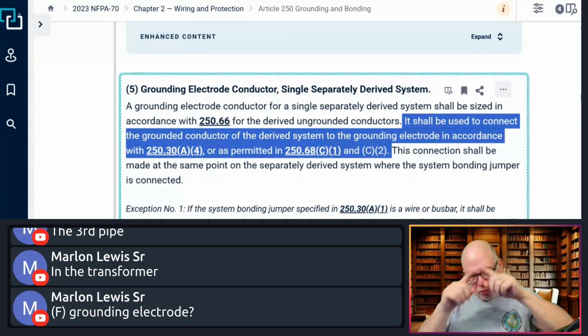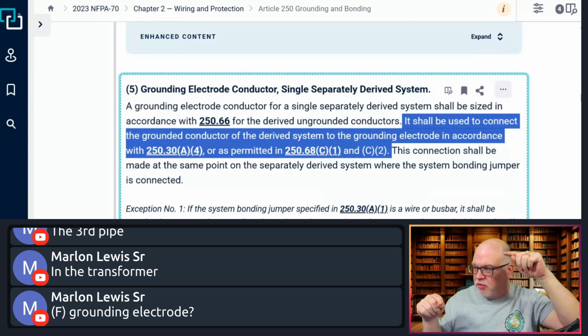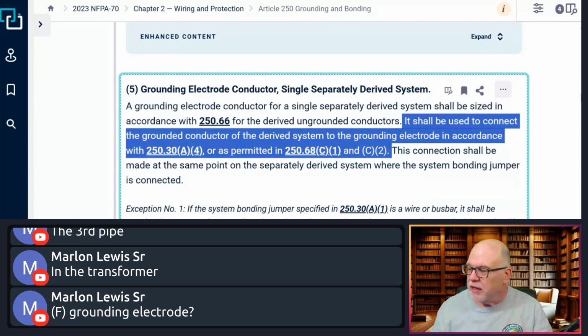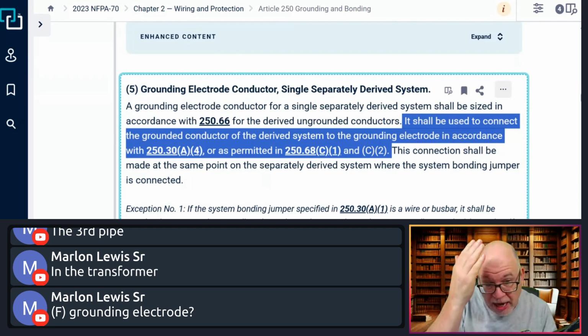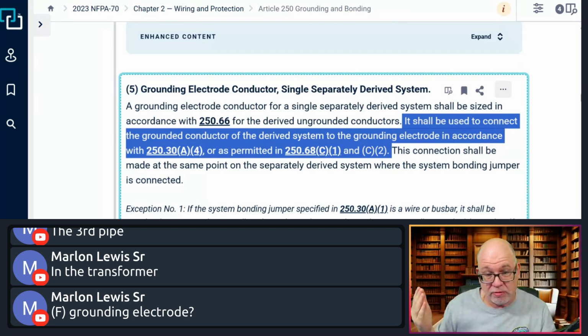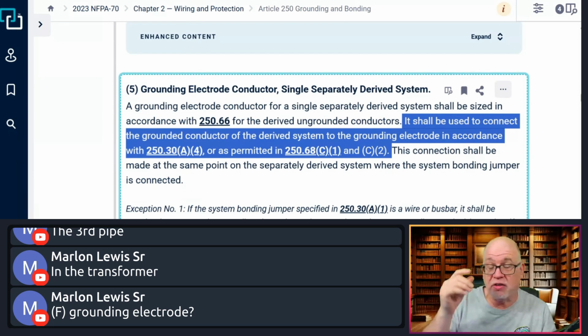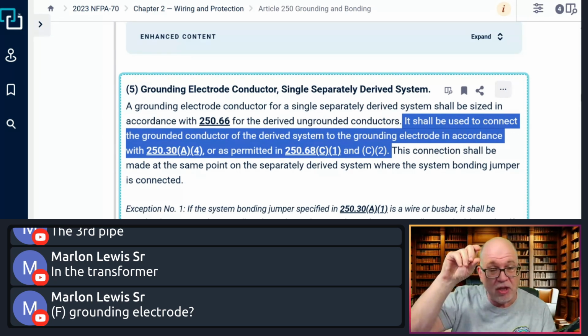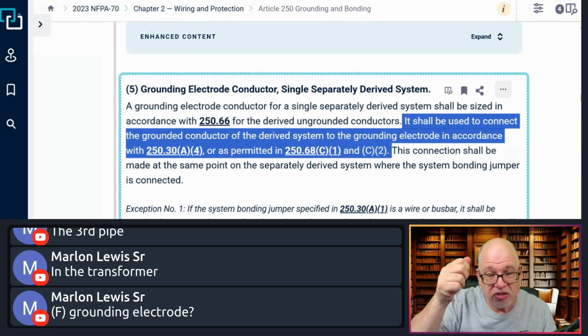Now, that's what the grounding electrode conductor is when it comes to a transformer. Typically that would connect right to the grounded conductor, like it says, straight from the grounded conductor to the electrode. That's what the code rule says. So that's why you have these extra lugs at the XO, because you may have two larger lugs and then one smaller lug, because that's where you take your GEC.